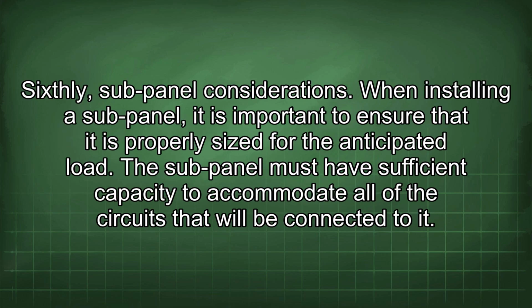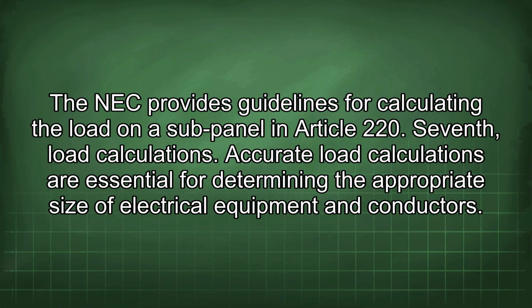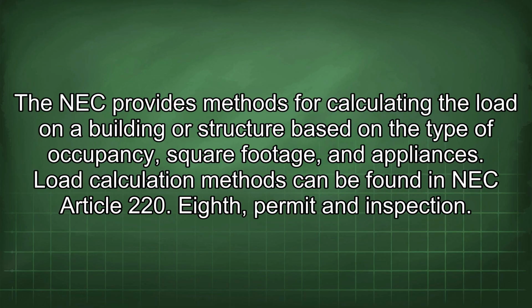Sixthly, sub-panel considerations. When installing a sub-panel, it is important to ensure that it is properly sized for the anticipated load. The sub-panel must have sufficient capacity to accommodate all of the circuits that will be connected to it. The NEC provides guidelines for calculating the load on a sub-panel in Article 220. Seventh, load calculations. Accurate load calculations are essential for determining the appropriate size of electrical equipment and conductors. The NEC provides methods for calculating the load on a building or structure based on the type of occupancy, square footage, and appliances. Load calculation methods can be found in NEC Article 220.